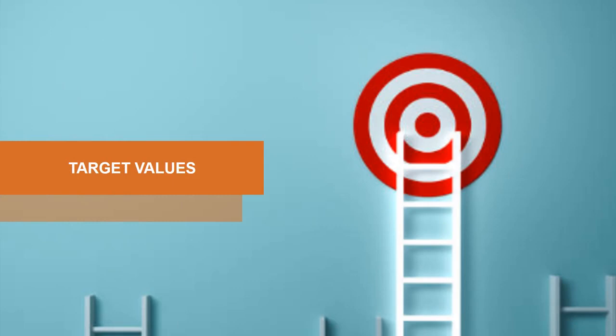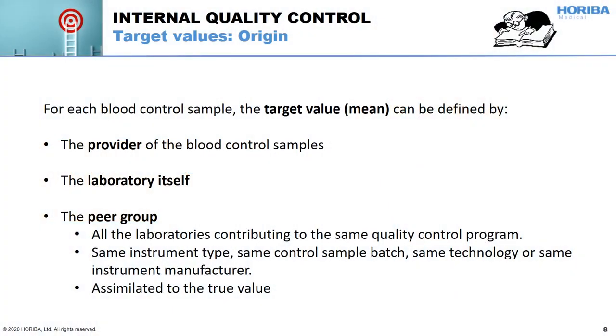These target values can have different origins. First, they can be delivered from the provider of the control samples. But it is also recommended for the laboratory to set its own target values and confidence ranges. The last possibility is that the target values come from the peer group, which corresponds to all laboratories using the same instrument and same technology — all similar laboratories which are part of the same quality control program.